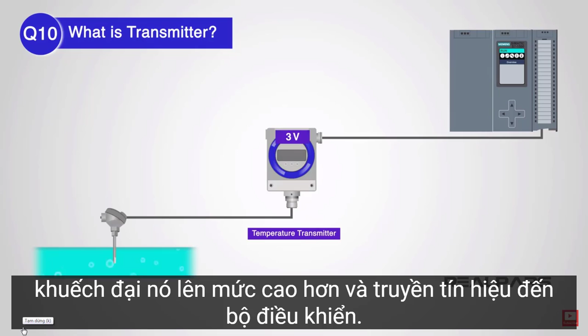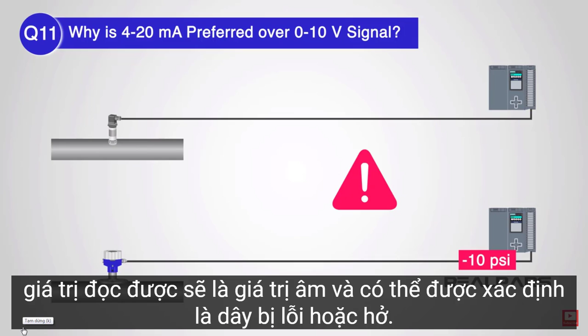Question 11: Why is 4 to 20 milliamp preferred over a 0 to 10 volt signal? Answer: the 0 to 10 volt signal tends to weaken over long distances due to resistance. The 4 to 20 milliamp signal can travel long distances without dropping value. If the signal drops below 4 milliamps, the reading becomes negative and can be identified as a fault or open wire.